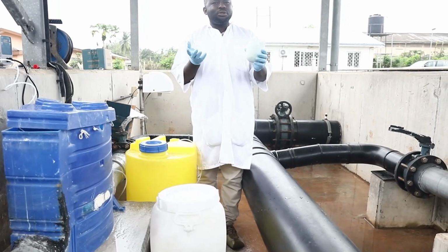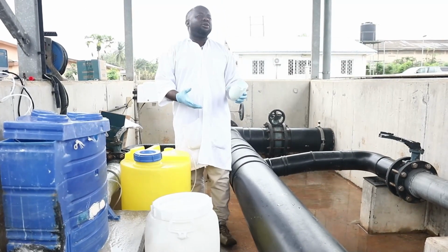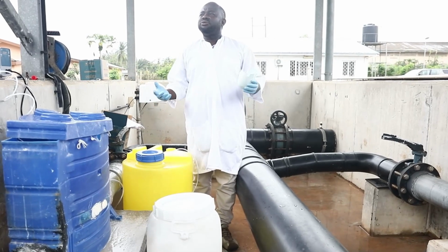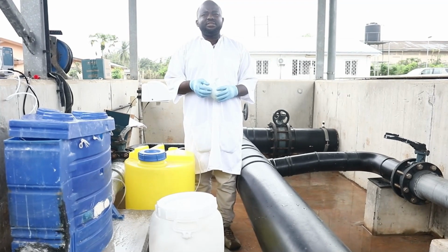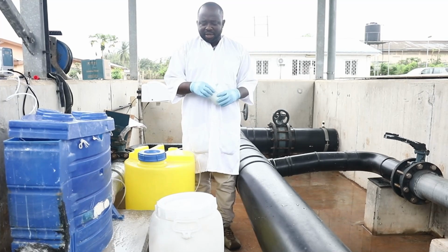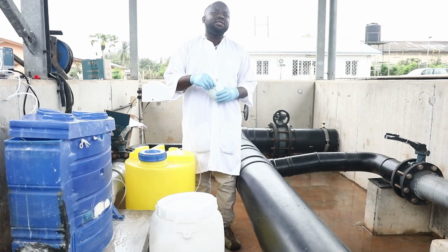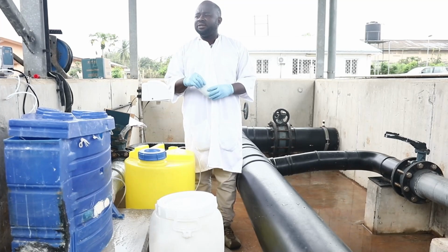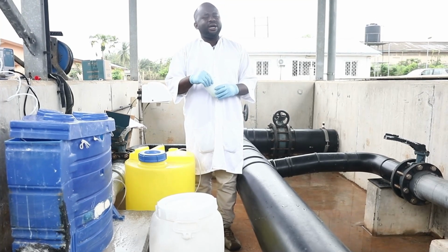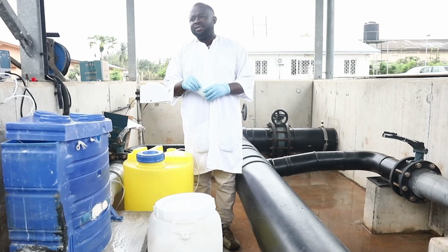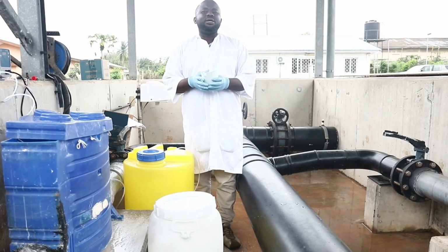At least you should know what you are measuring. The main idea is that we are also trying to avoid wastage. So whatever we are putting in there, we should know how much we are disinfecting. And this should be taken seriously, because when you overdose chlorine, we have something we call byproducts, the chloramines and all that, the trihalomethanes, which are carcinogenic. That is why it's very critical that we measure and know the quantity.